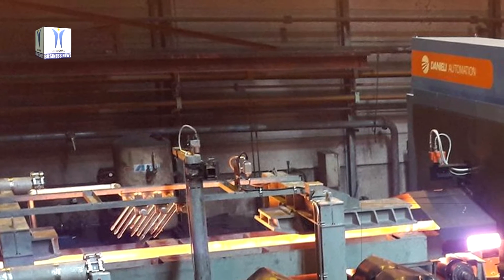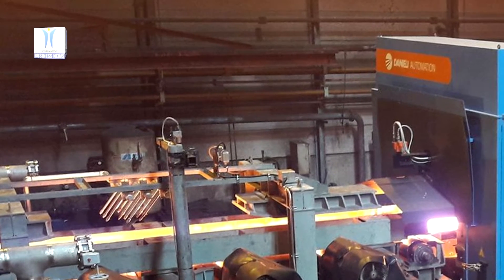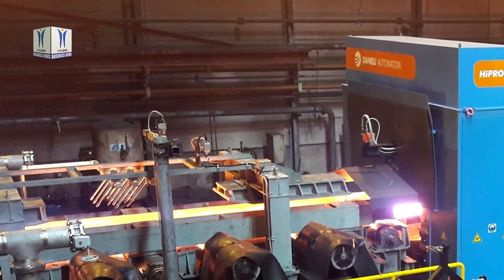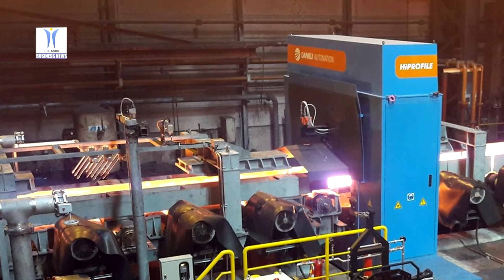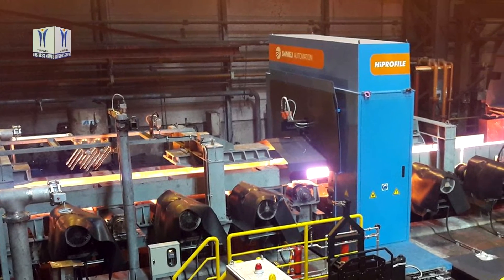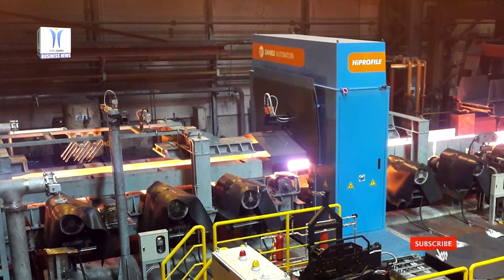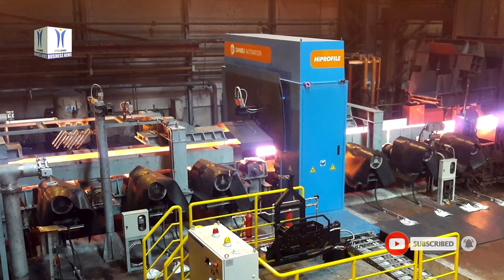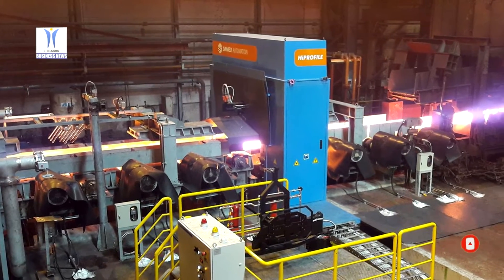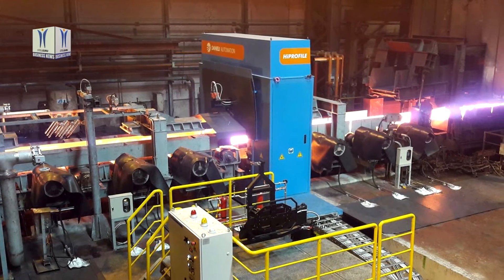HiProfile allows the complete in-line dimensional control and surface defect inspection of bars and sections during rolling. The system, featuring ultra-high-speed laser heads capable of acquiring several hundred profiles per second, allows real-time 3D representation of the bars, accurate dimensional control, and integrated surface defect detection during rolling.